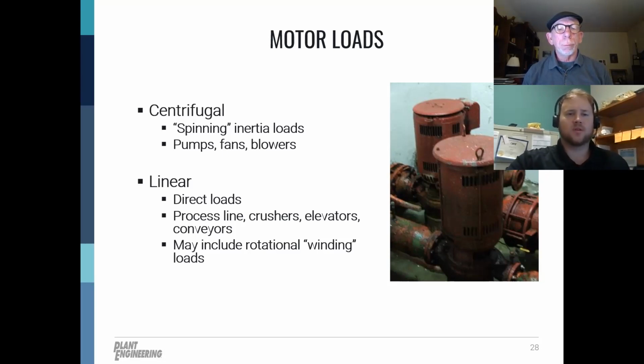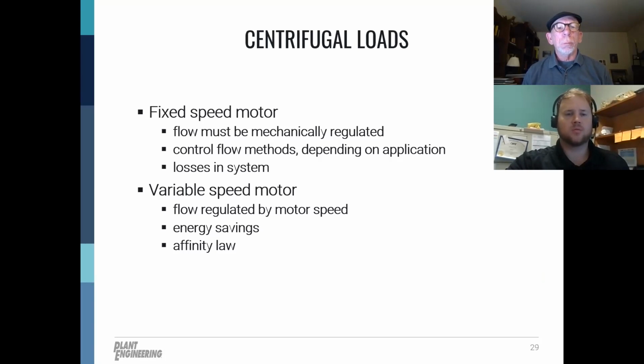So we talk a little bit more specifically about centrifugal loads. There are generally two types of motors with centrifugal loads: the fixed speed motor and variable speed motor. So for a fixed speed motor, the output air or liquid flow is going to be regulated mechanically by valves or dampers. And so there's a lot of innate losses in this type of system. But if you use the variable speed motor for the same system, the output air or liquid flow can be regulated by motor speed. So, we've done a presentation here before on energy savings and a lot on variable frequency drives. If you're able to do this, use a variable speed motor or inverter duty motor, you have a lot of energy savings based on affinity laws.